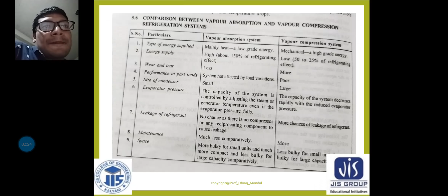The Electrolux refrigerator, that means the aqua ammonia refrigeration system or three fluid system, was discussed, and today we are going to discuss the lithium bromide absorption system. There are mainly two drums. In one drum there is a condenser and a generator, and in another drum the evaporator and the absorber are placed. This is because the generator and condenser operate at the same temperature and pressure, and the evaporator and absorber operate at the same pressure.